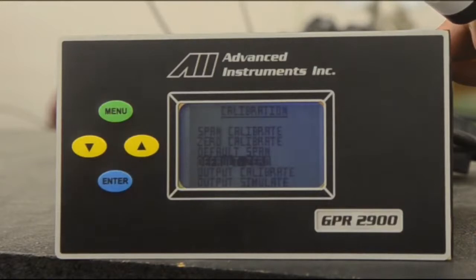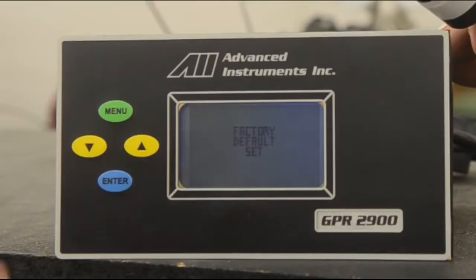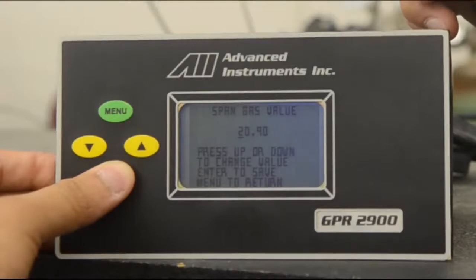This essentially eliminates any prior calibrations done to the analyzer at the factory and is advised to be done when you install a sensor. Repeat the process with the default span option, hit enter, and again, factory default set will appear. Once that is done, scroll up to span calibration and hit enter. As you can see, the value 20.9 is already preset at the factory. This is done because this is the amount of oxygen present in ambient air.